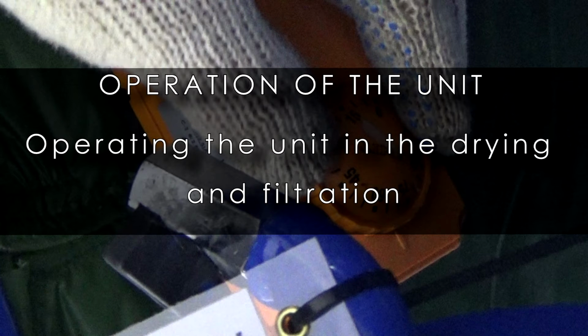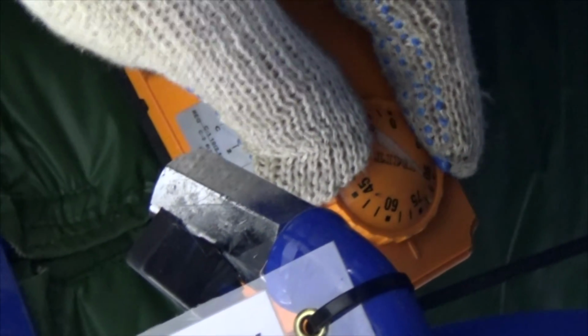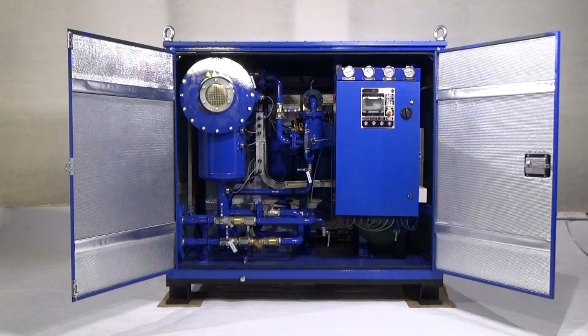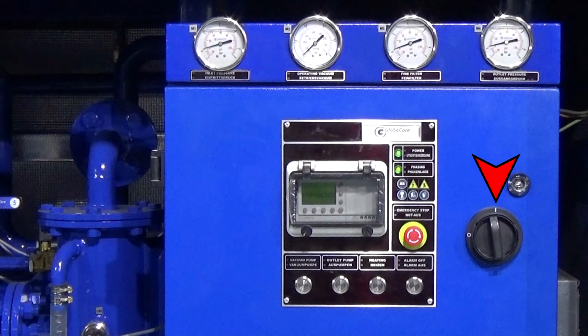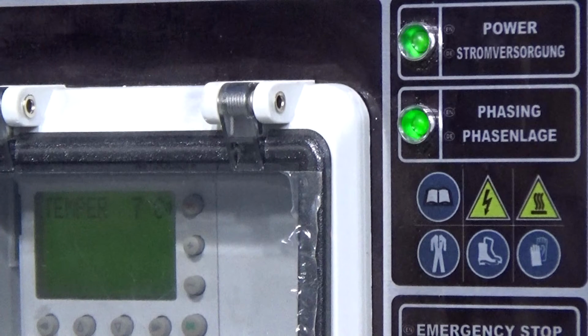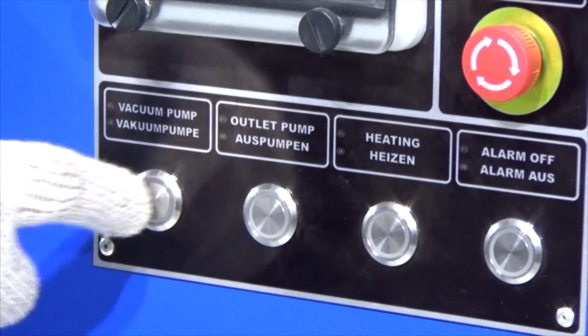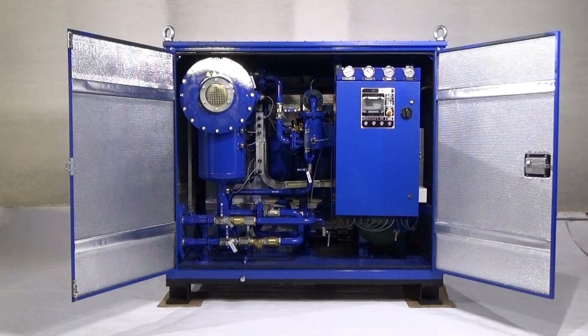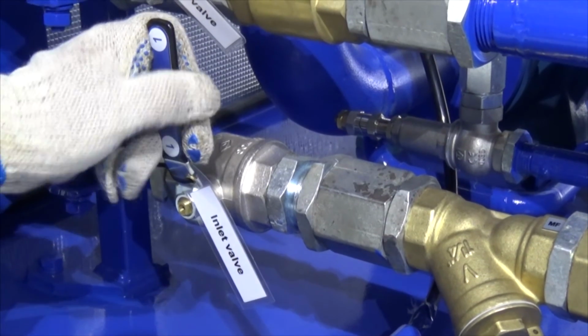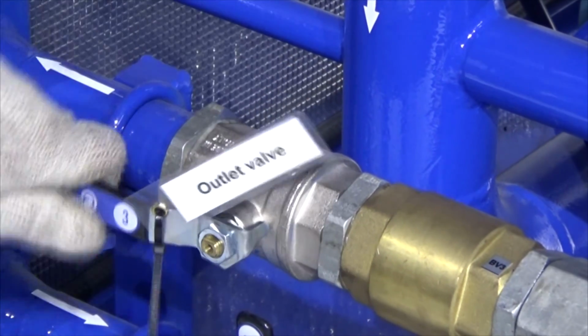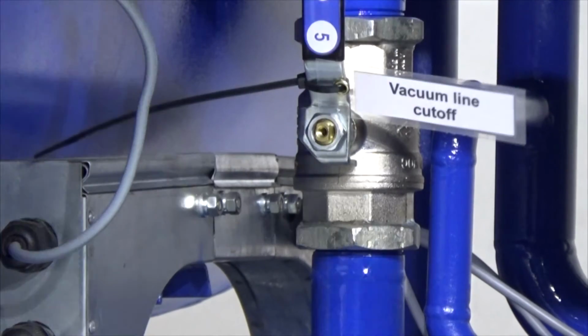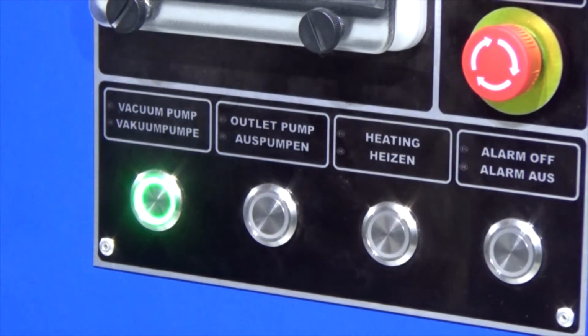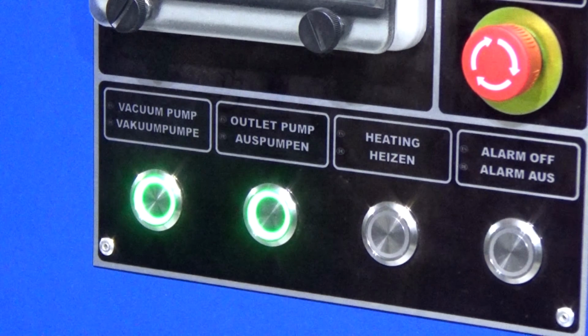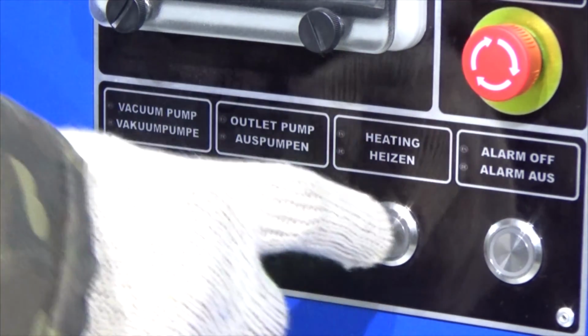Operation of the unit. Operating the unit in the drying and filtration mode. 1. Set the thermostat to the 70°C mark. 2. Power the unit by turning the power handle to the on position. Power and phasing lights must be on. 3. Start the vacuum pump by pressing the vacuum pump button. 4. Open valves MV1, MV3, and MV5. The unit will start to fill with oil. 5. Start the output pump by pressing the outlet pump button. 6. Engage the heater by pressing the heating button.